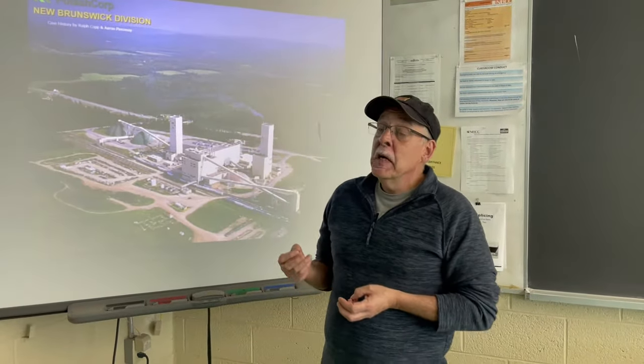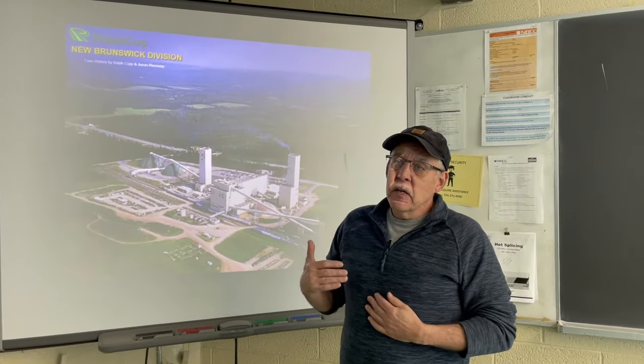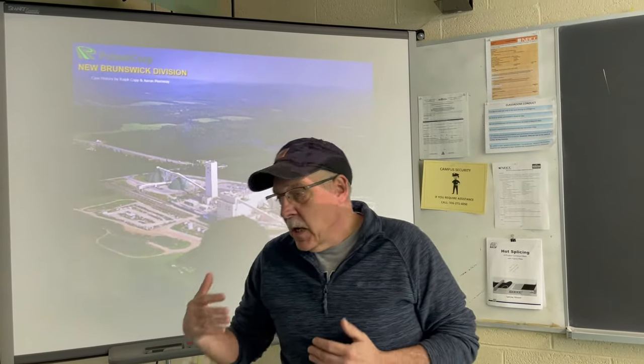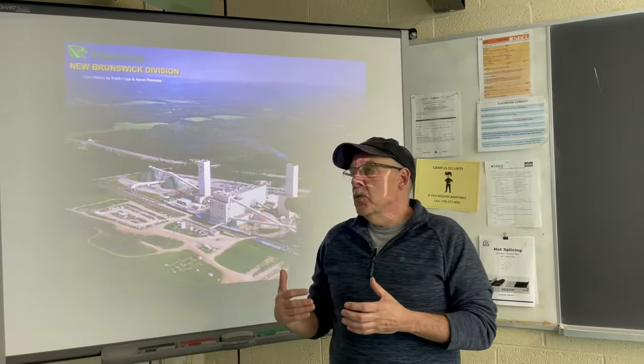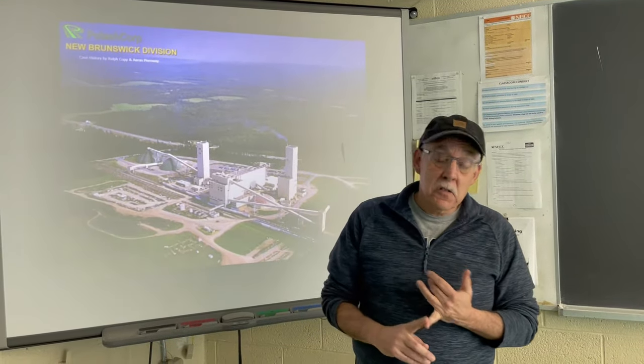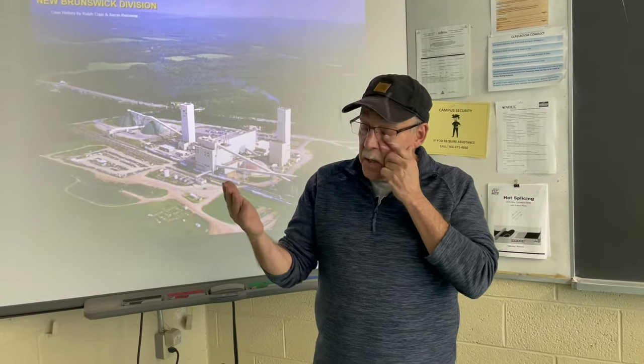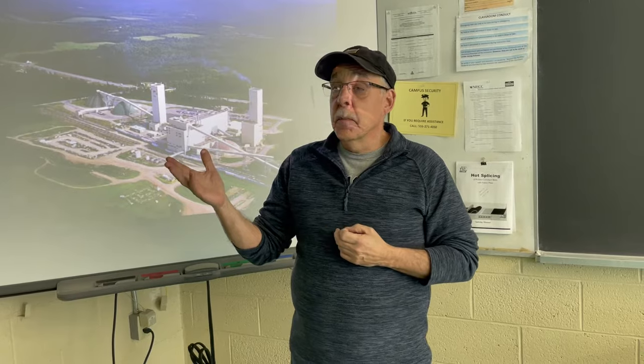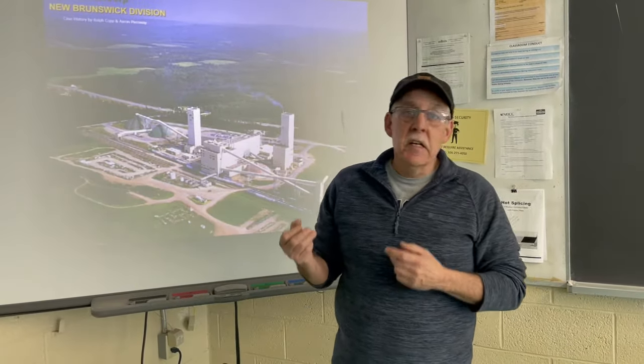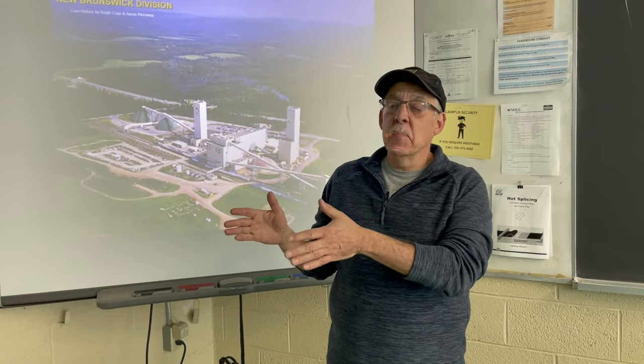The one we're mainly concerned with is vibration, but in any good predictive maintenance program, we use other technologies with the vibration to verify some of our faults. One of the technologies we use is oil analysis. When I see vibration go up, or I see a problem in a piece of equipment, the first thing I ask for is an oil sample, because the particles in that oil can tell me a lot about what's wearing in that piece of machinery.